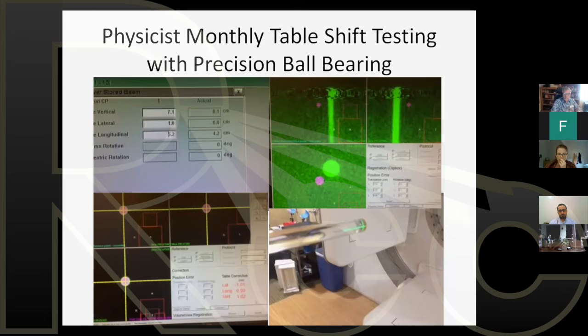shifts. Now, the therapists, I know the therapists daily are checking table shifts, but does the physicist check table shifts? And I never want to be in a position where the therapist is checking things that I don't double check. So the therapists are doing a great job checking table shifts on a daily basis, but I like to come in once a month and run this ball bearing Winston-Lutz test to make sure that KV-MV isocenter are the same and that the shifts are working correctly.